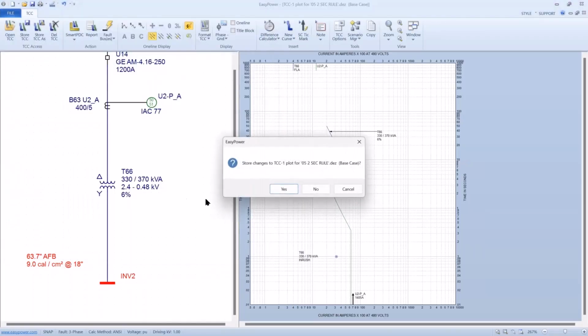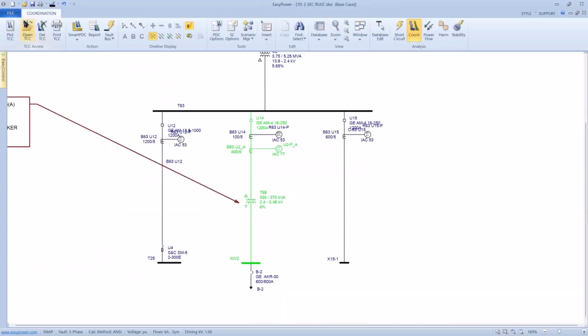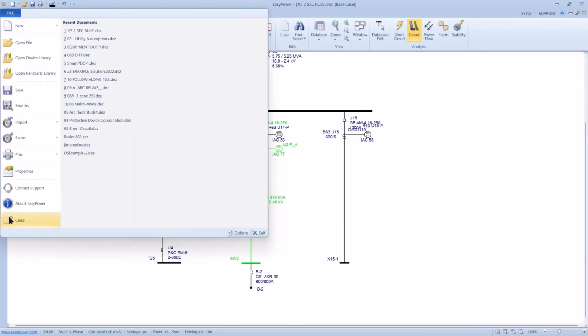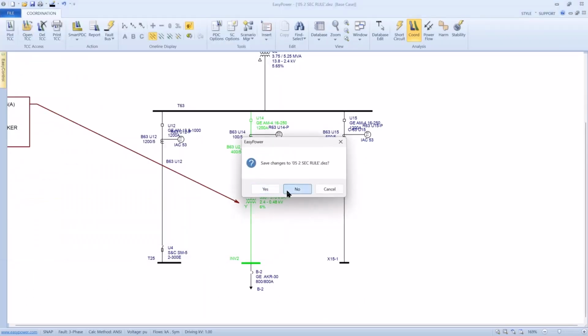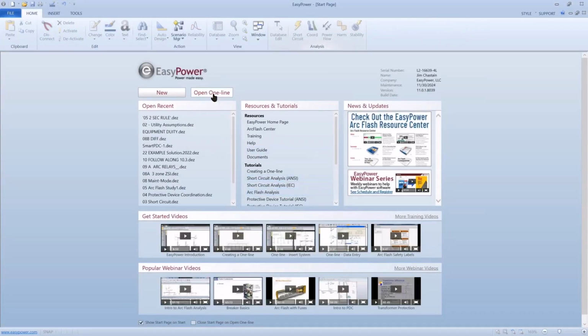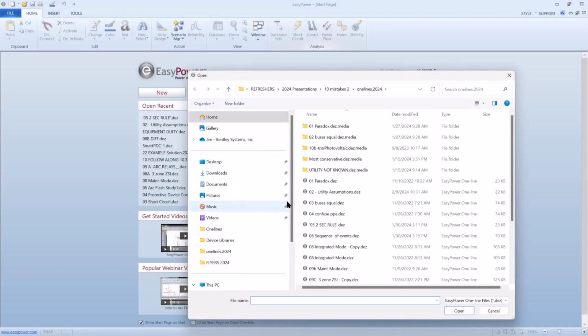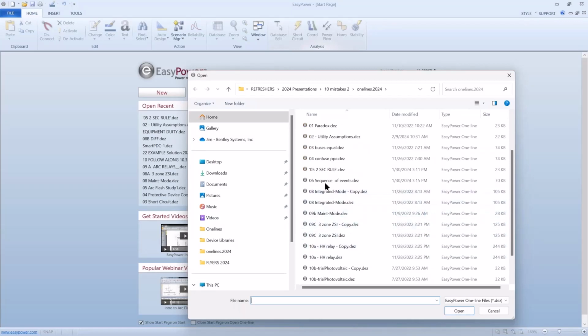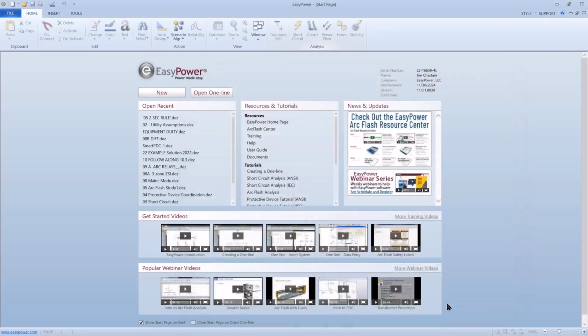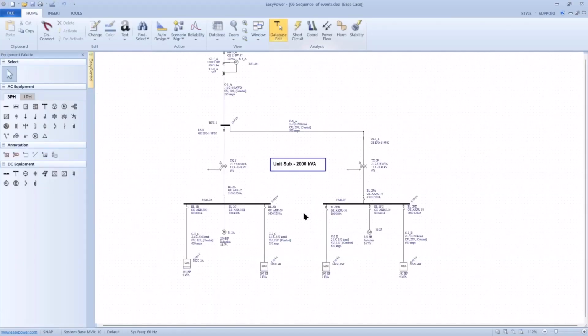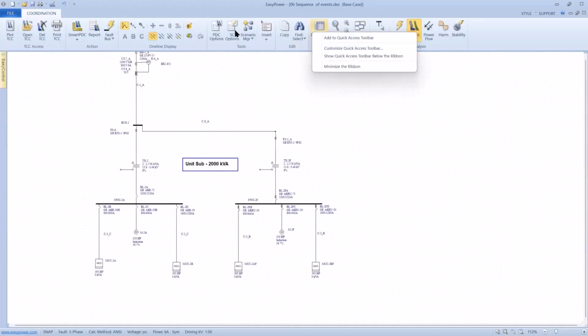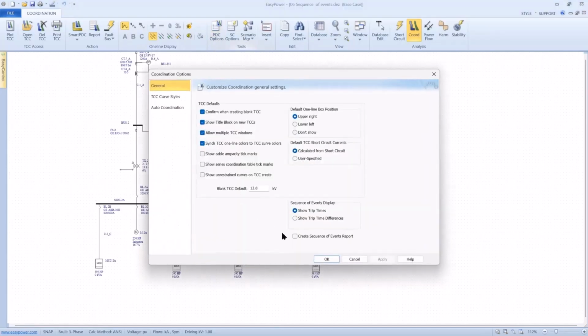So again, these are very much subjective, and there's nothing that says this is the only way to do it. I'm just offering suggestions that you may want to make sure you're not obscuring miscoordination by prematurely going to 2 second max. And so I'm looking for my sequence of events. It could be a very complex system that we're looking at, but at the very least, if I go to coordination, looking at current, I'm going to ask for a sequence of events report to be created.